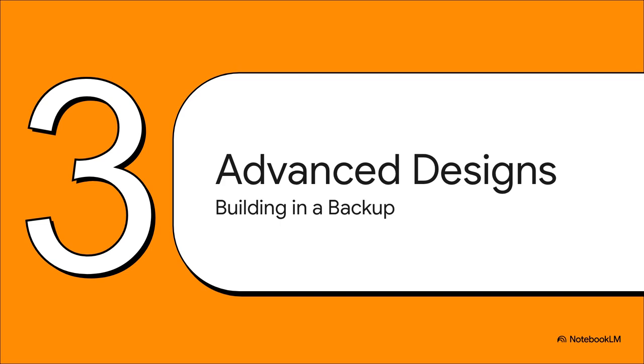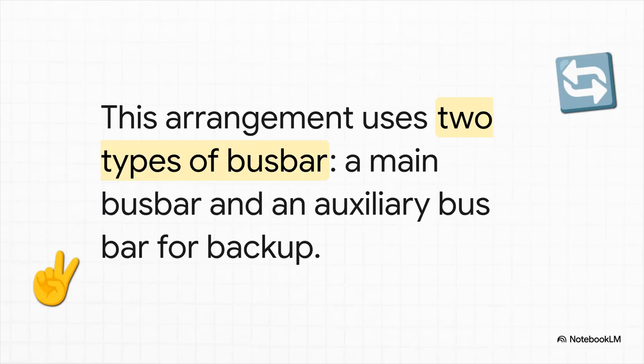You need a proper, dedicated backup plan, and that's where the more advanced designs start to come into play. Let's talk about the main and transfer bus system. With this setup, you have two busbars running right next to each other, in parallel. You have the main bus, which is doing all the heavy lifting, and then you have a transfer or auxiliary bus, which is just on standby, ready to go as a backup. This is where we introduce that really critical concept of redundancy.